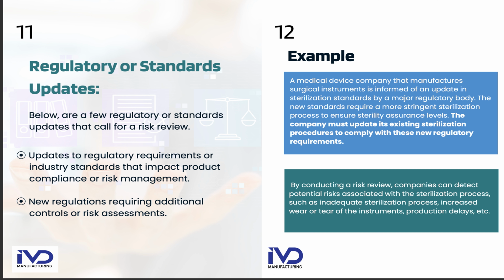So what you need to do, my friends, is conduct a risk review, and the company needs to detect potential risks associated with the new sterilization processes, such as inadequate sterilization, increased wear and tear of the instruments, and production delays.